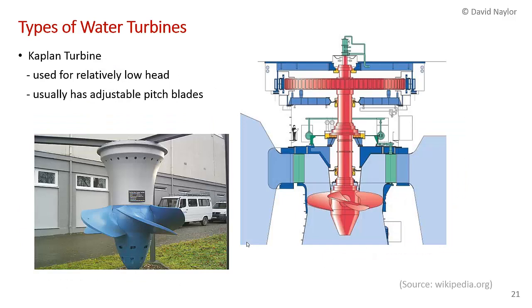The last type is the Kaplan Turbine, used when there is a relatively low amount of head — not a lot of water height available to generate large pressure forces. The blades of a Kaplan turbine are adjustable in pitch so that the water attacks the blade at just the right angle to achieve maximum efficiency. Those are the three common types of turbines used to generate electric power. We've covered the general energy equation and done an example calculating power output from a turbine, which completes Chapter 3.